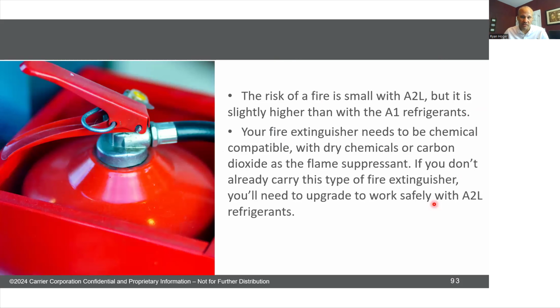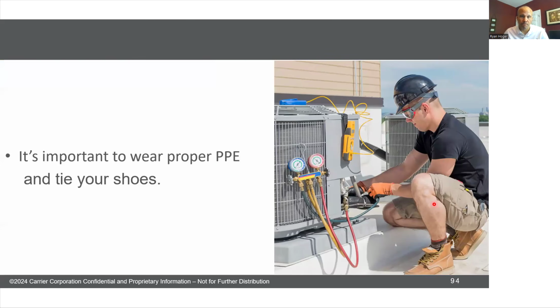When you go inside and start brazing stuff in the building, you need to bring your fire extinguisher inside, right? That is already a rule with A1 refrigerants. You have to do it still with A2Ls, and it's obviously slightly more important.